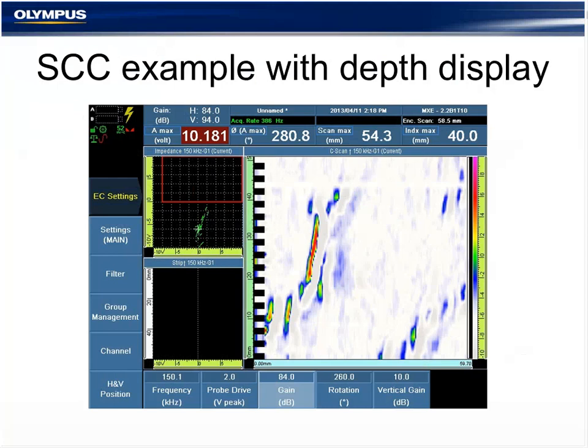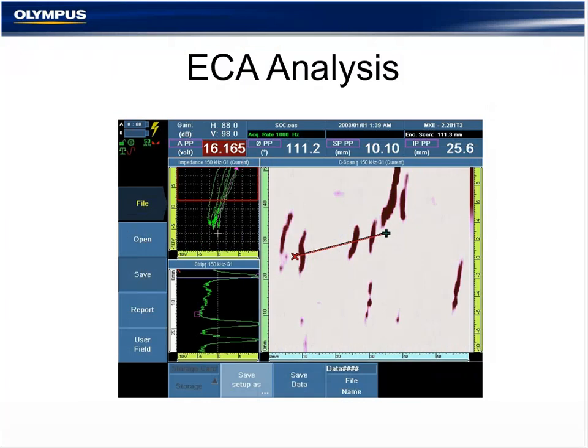That's an actual stress corrosion cracking pipe being scanned with eddy current array, showing different depths. It can also be configured as a go, no-go. So we have this nice color palette here looking like a penetrant testing scan. Basically, what's white is good, what's red is bad. It's as easy as that. And when taking that cursor in analysis mode, it's going to display the impedance view and the strip chart. For an eddy current analyst, that's going to mean something, and he's going to be able to identify and tag those defects accordingly.